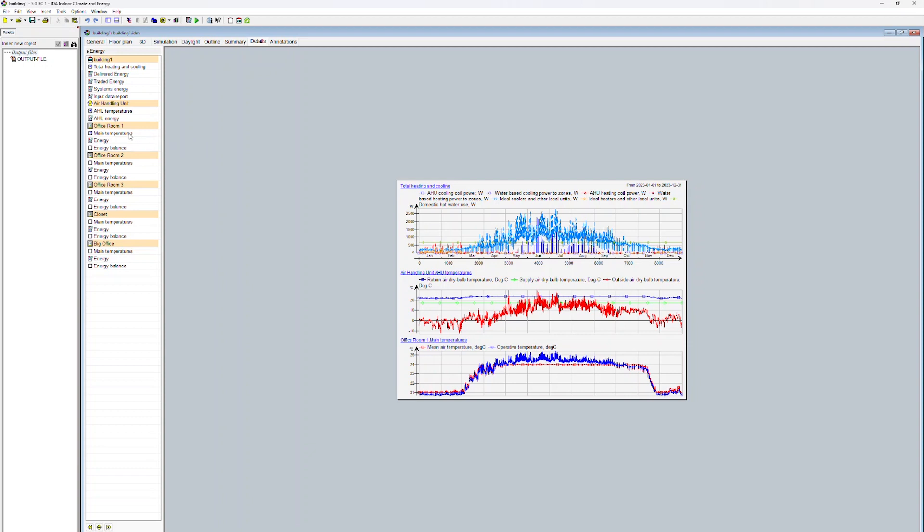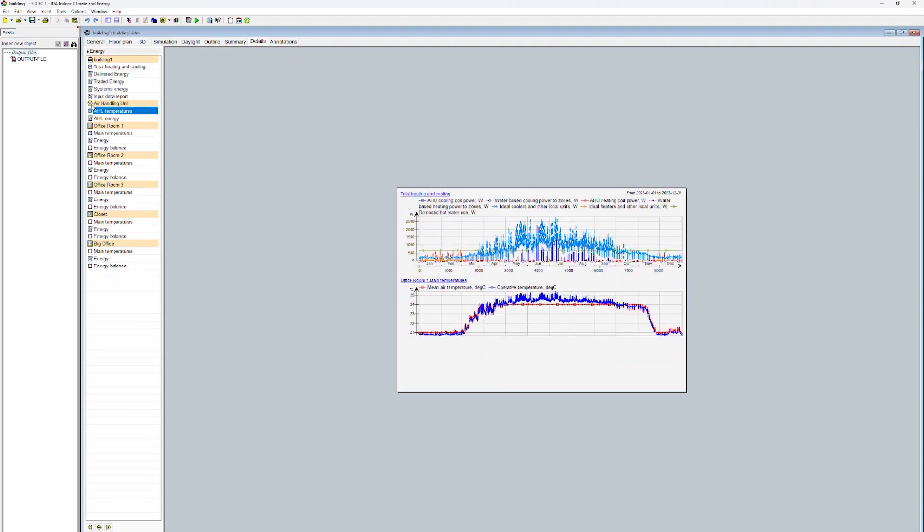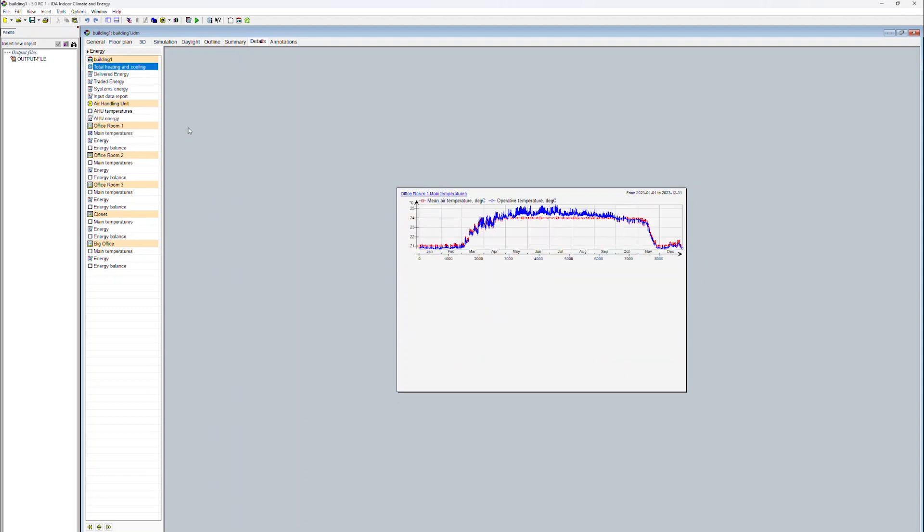The operative temperature is calculated based on the mean air temperature and the mean radiant temperature. The mean radiant temperature is derived from the surface temperatures and the calculation is based on the area weighting.